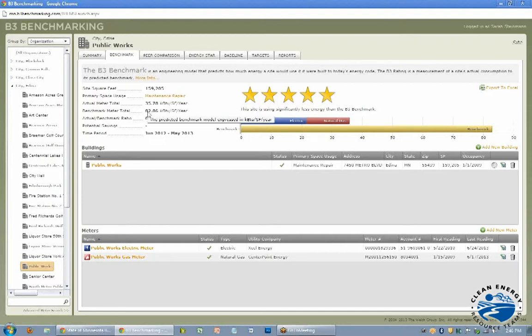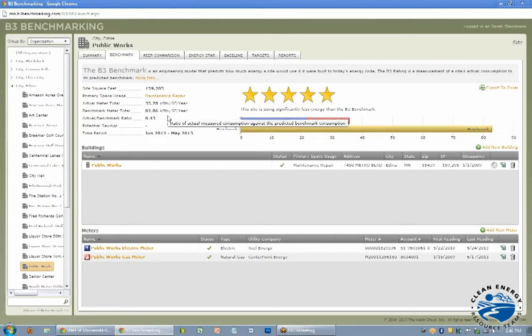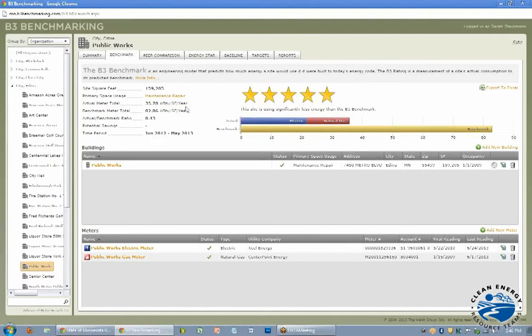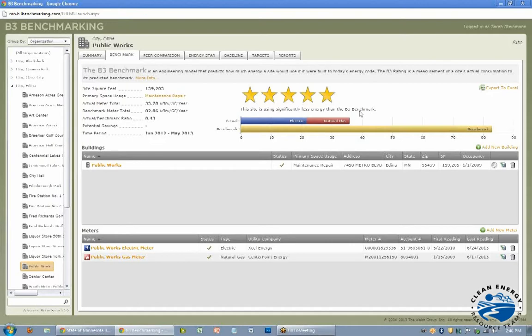So they're estimating that a building of this size and this usage type would use 82 KBTU per square foot per year. So the building is using quite a bit less, about less than half of what it's expected to use. So you can see here it's got a lot of stars because it's using significantly less energy than the benchmark.